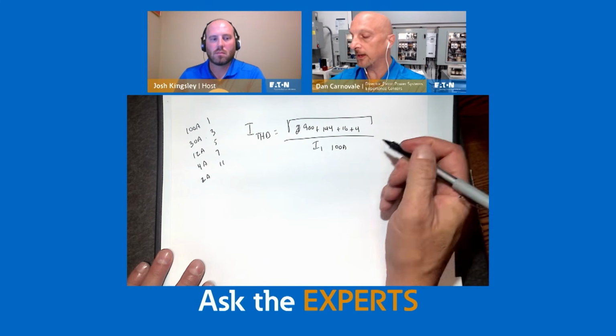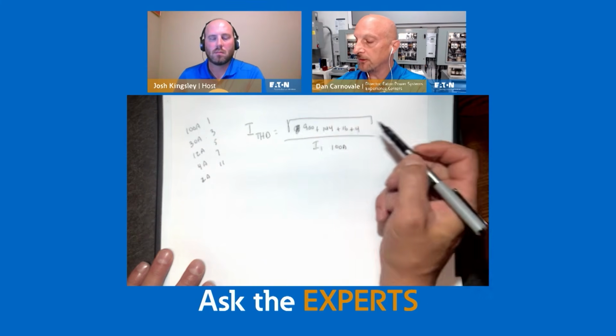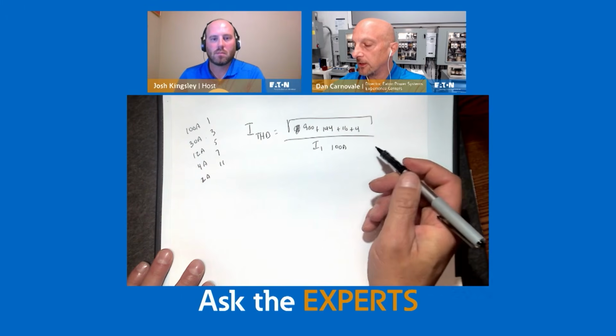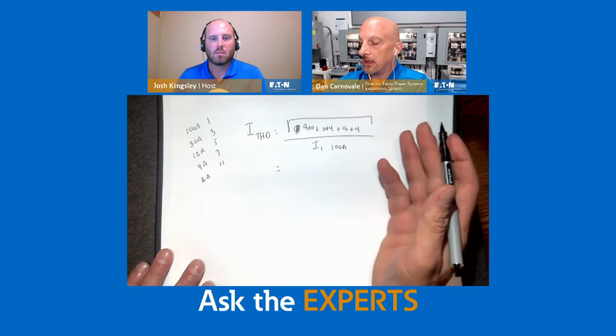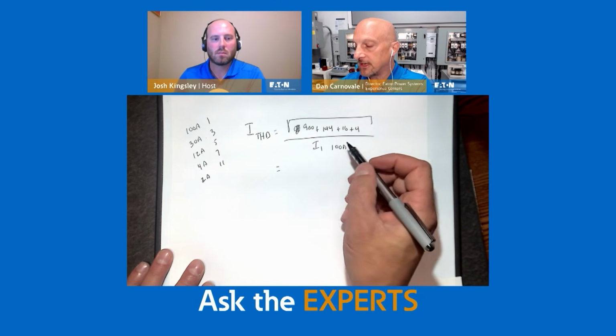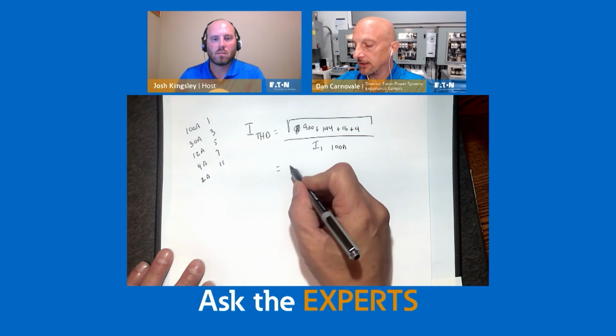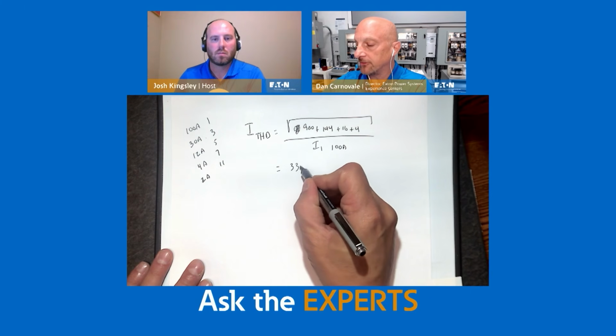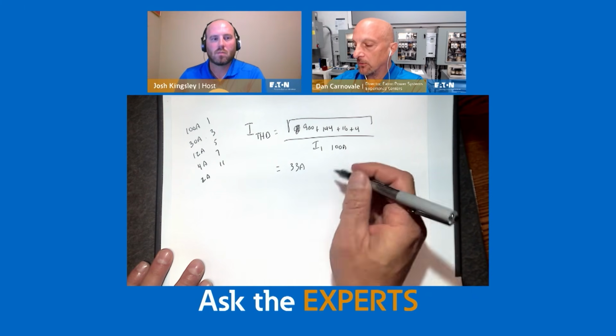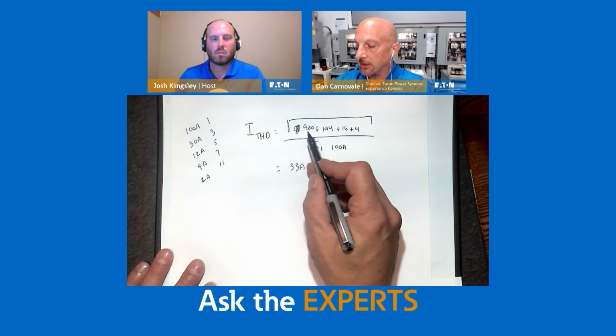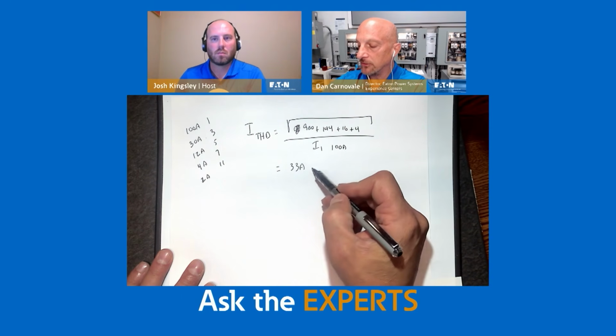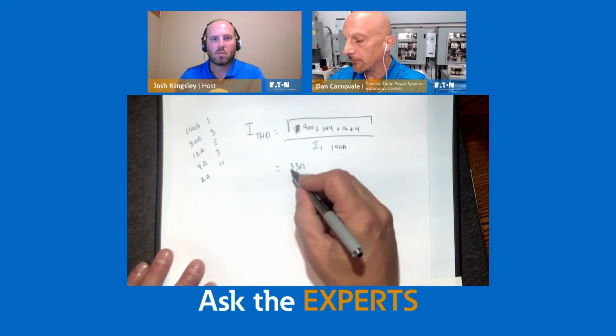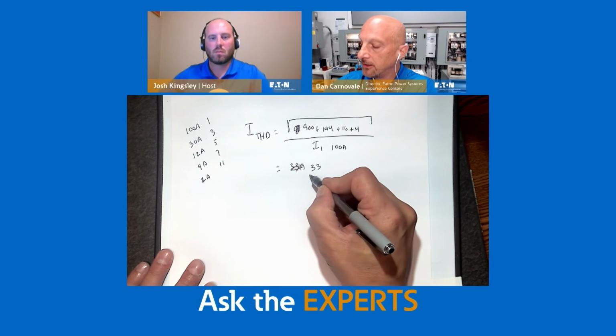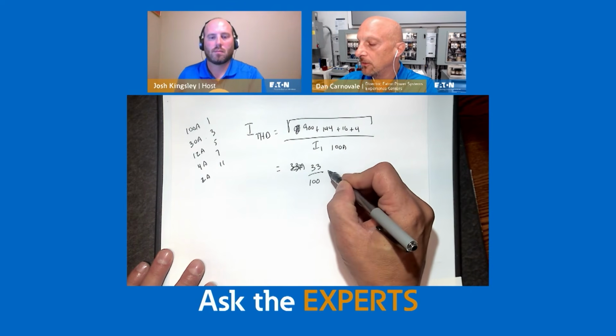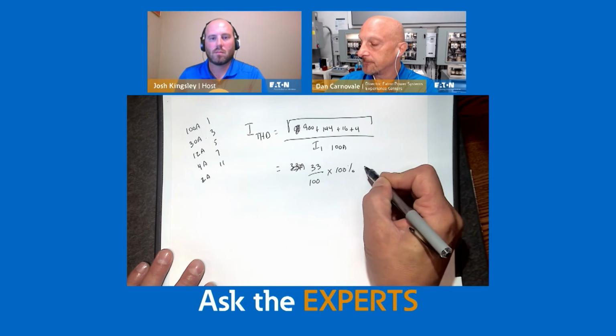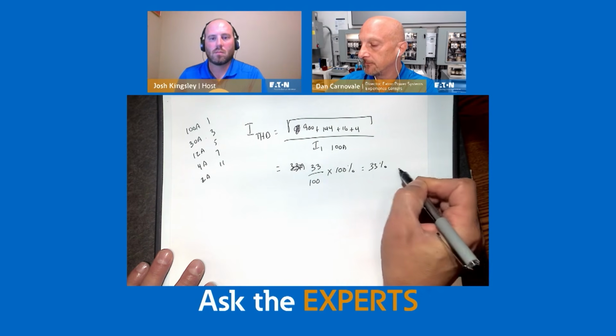What you'll notice right away is that when you square these terms, the biggest ones really become the predominant ones. I don't have my calculator handy, but I would guess you get somewhere in the 30s, say 33 amps. It's not really relevant to have the exact numbers here. Once you add it together and take the square root, say you get 33. 33 divided by 100, multiplied by 100%, gives us 33% THD.